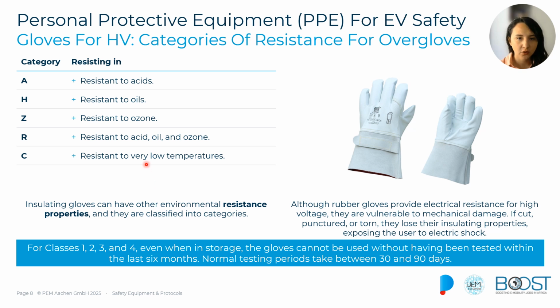For higher class gloves, we usually do this periodic testing, and as a general rule, if the glove is punctured or if it loses insulation properties, or if we see, for instance, a scrape, in those cases when we notice any damage, we do not use those gloves. Also, many people tend to try to repair the gloves, but this is not recommended either. What we have to do is to replace them and to ensure that we are wearing reliable protection.